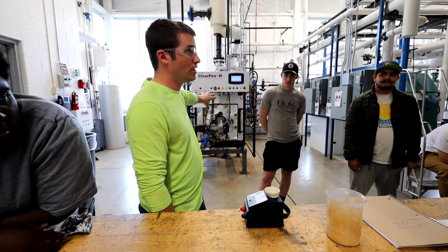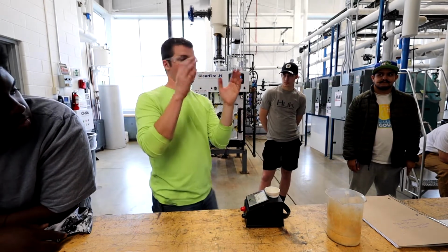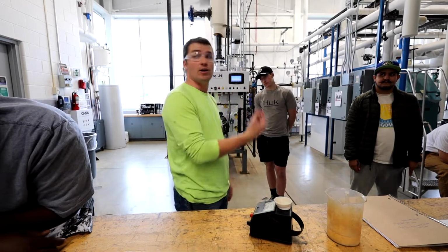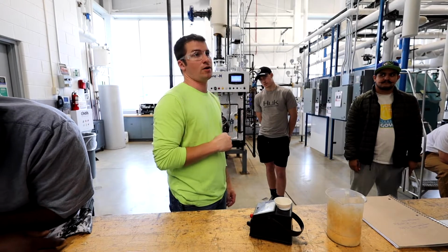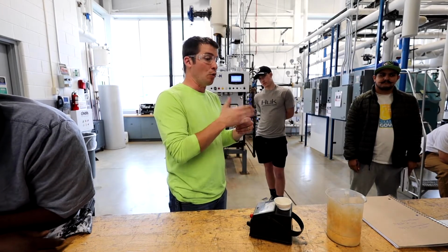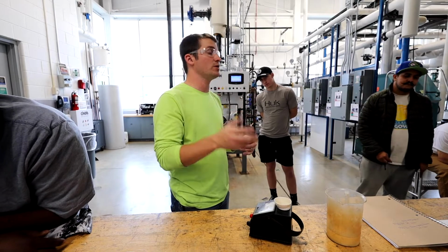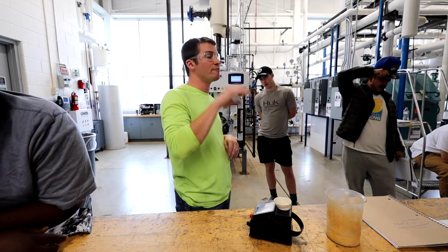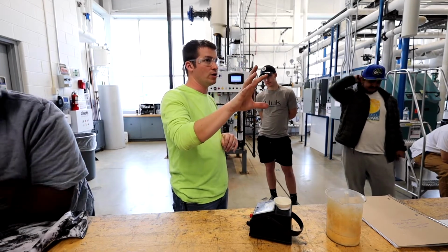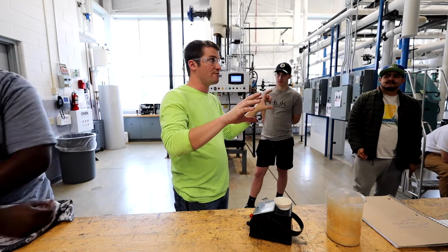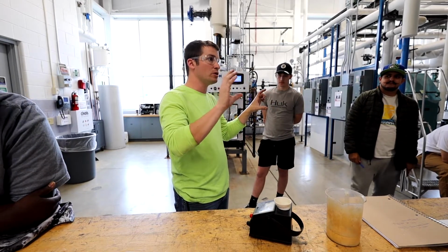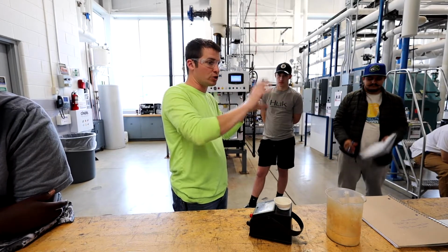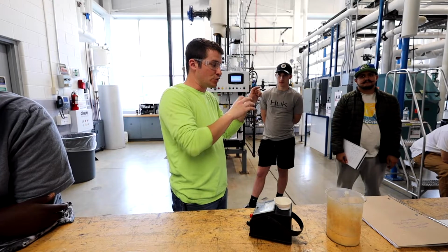Same thing's happening in your boiler. We're taking feed water, which is gonna have a conductivity of whatever it is, right? And we'll test that. Let's say it's 100 for easy math. And in our boiler, we're gonna have a couple thousand on our conductivity, right? So we wanna try to run that as high as we can safely because it maximizes the use of water, right? We're gonna use less water. If I have 10 cycles of concentration in my boiler versus a boiler that's running 5 cycles of concentration, at 10, I'm literally using half as much water and chemical as I am at 5, right? So the goal is you want to try to get it higher to reduce that stuff.